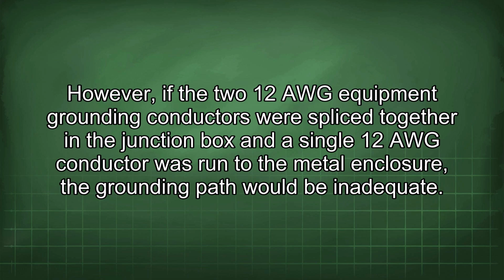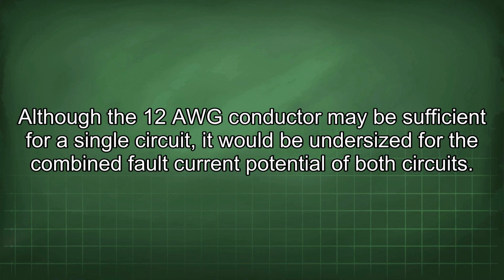However, if the two 12 AWG equipment grounding conductors were spliced together in the junction box and a single 12 AWG conductor was run to the metal enclosure, the grounding path would be inadequate. Although the 12 AWG conductor may be sufficient for a single circuit, it would be undersized for the combined fault current potential of both circuits.